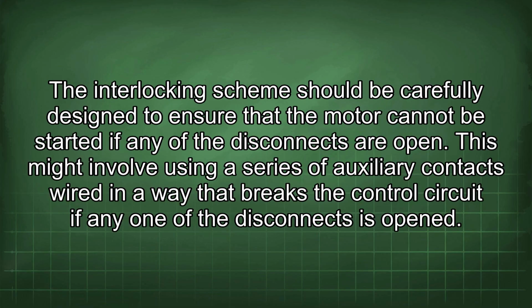The interlocking scheme should be carefully designed to ensure that the motor cannot be started if any of the disconnects are open. This might involve using a series of auxiliary contacts wired in a way that breaks the control circuit if any one of the disconnects is opened.